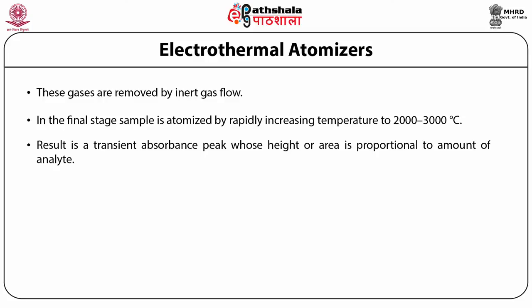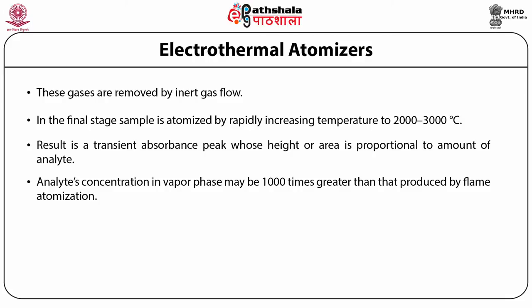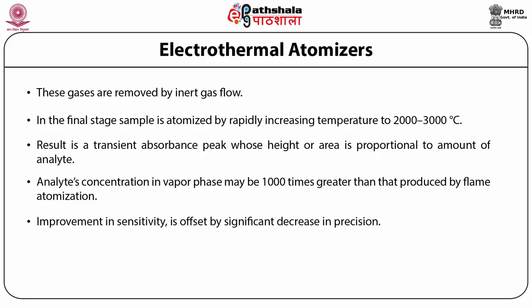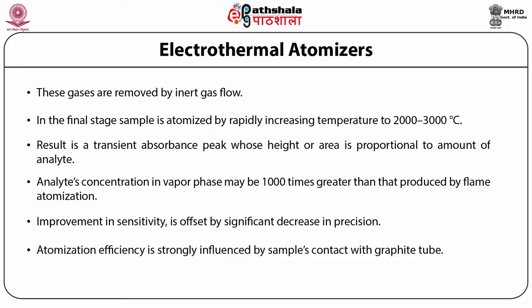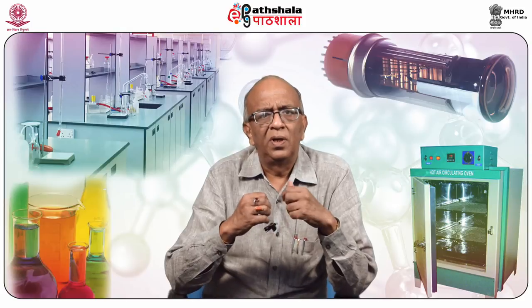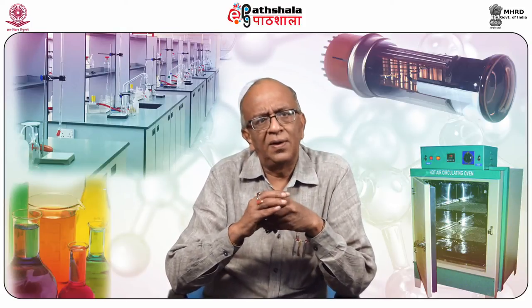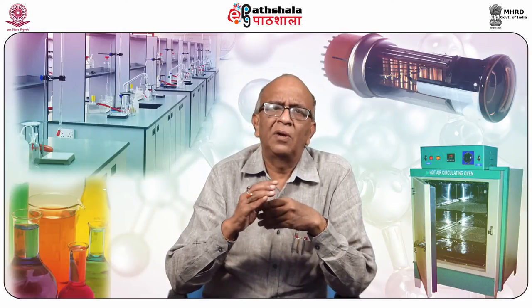Electrothermal atomization provides a significant improvement in sensitivity by trapping the gaseous analyte in the small volume of the graphite tube. The analyte's concentration in the resulting vapor phase may be as much as 1000 times greater than that produced by flame atomization. However, the improvement in sensitivity and detection limit is offset by a significant decrease in precision, because atomization efficiency is strongly influenced by the sample's contact with the graphite tube, which is difficult to control reproducibly.